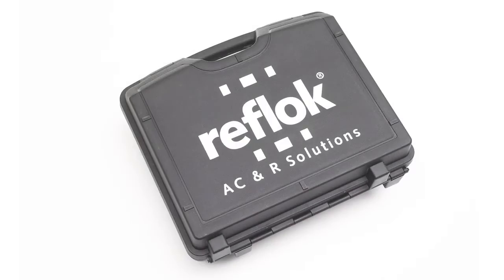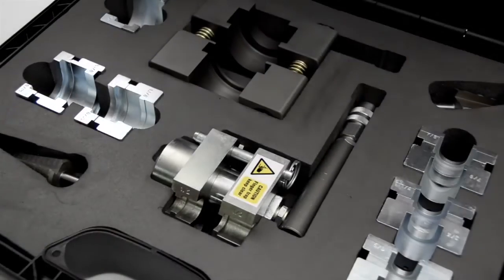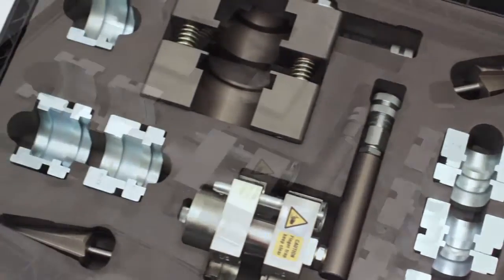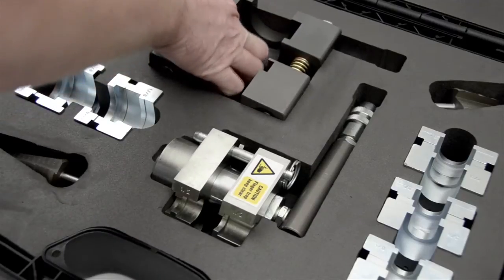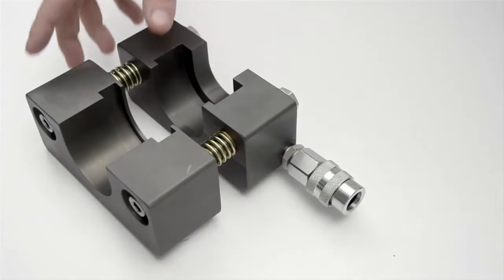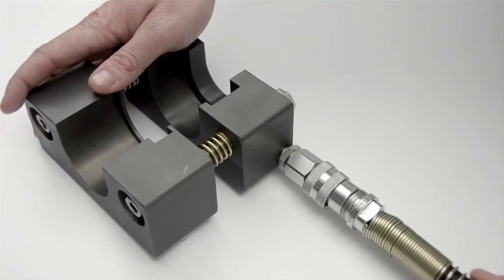The Reflok toolkit contains two joint-making tools: the larger linear tool for 5/8 inch to 1 and 5/8 inch joints, and the smaller rotary tool for joints from 1/4 inch to 5/8 inch. To make a joint from 5/8 inch to 1 and 5/8 inch, select the linear tool.